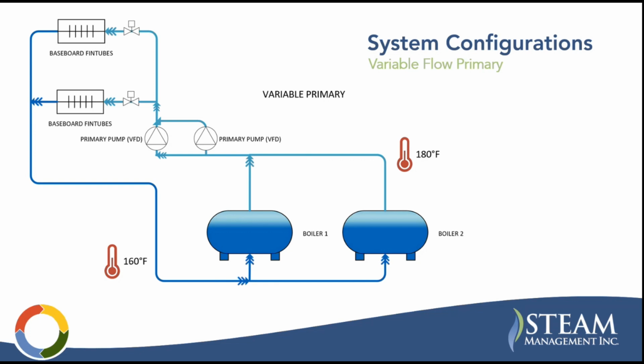The advantages here: you have fewer pumps than the primary secondary system, which we'll talk about next. So it's a little bit easier on maintenance and things like that. Lower installed cost, lowest pump energy. And one of the reasons it's recommended for condensing boilers is it ensures this minimum return temperature because there's no blending of that return line.